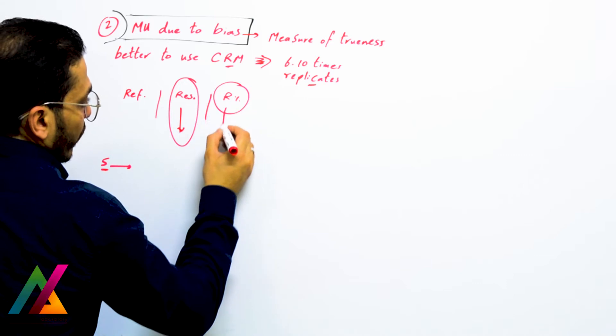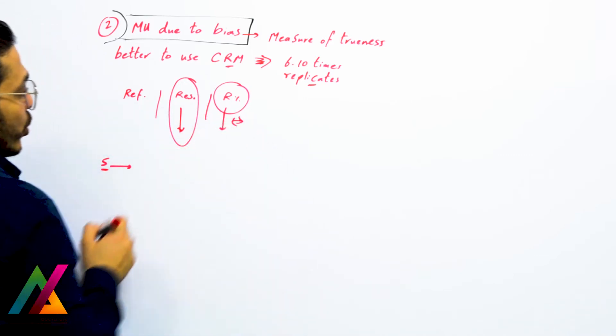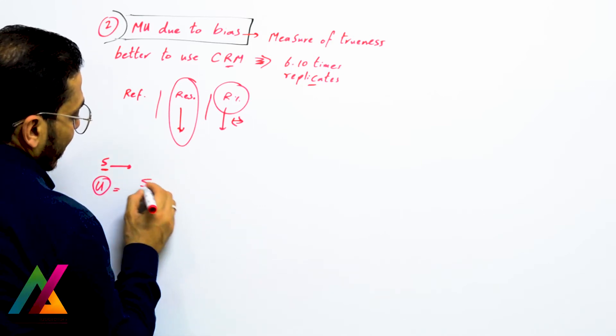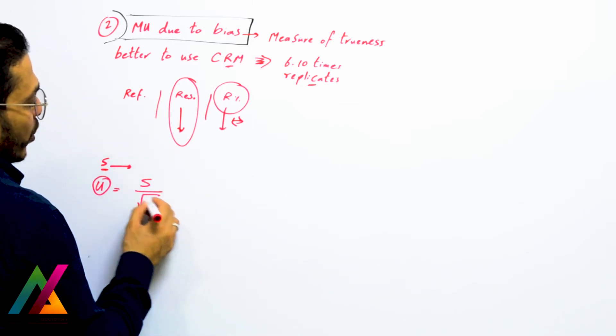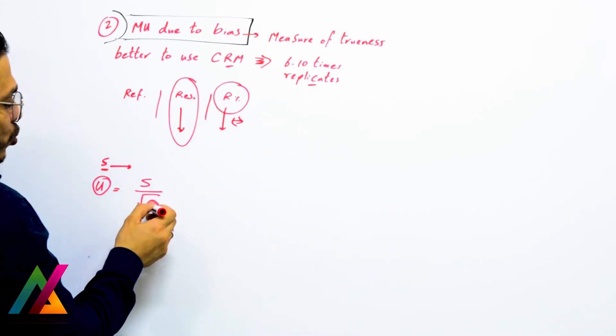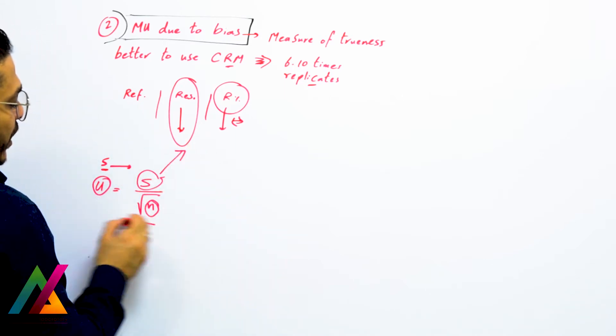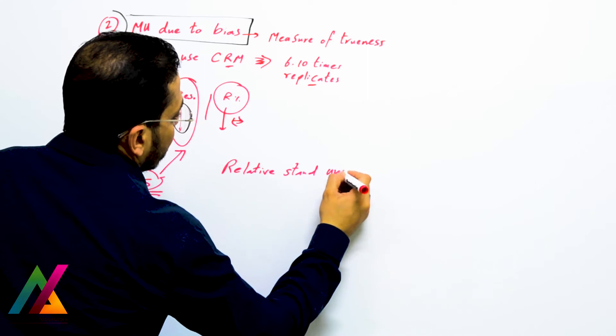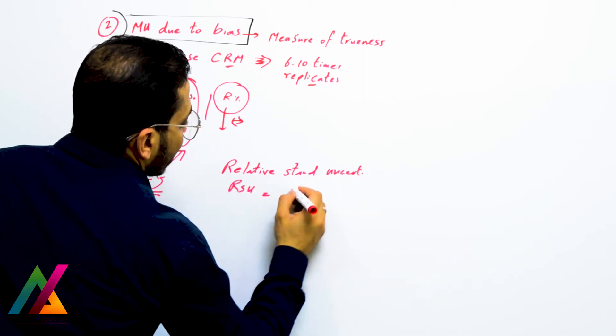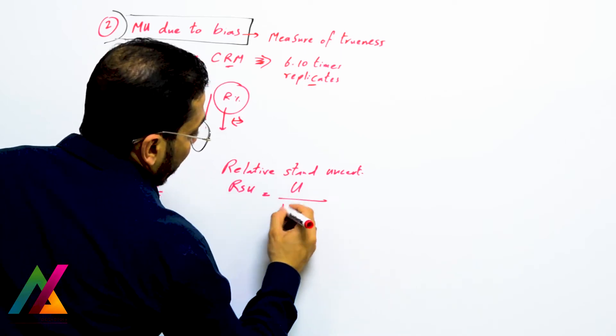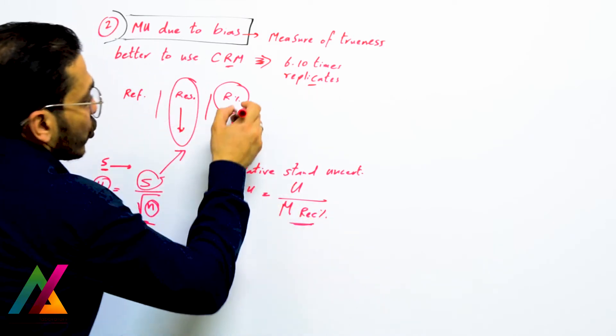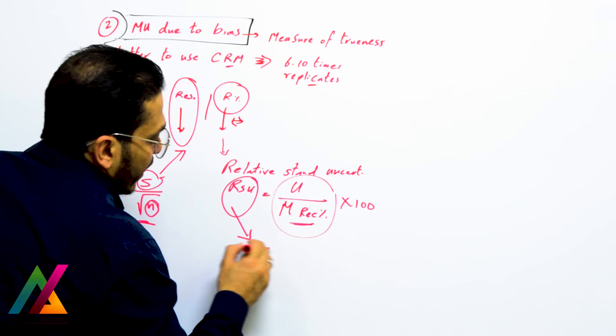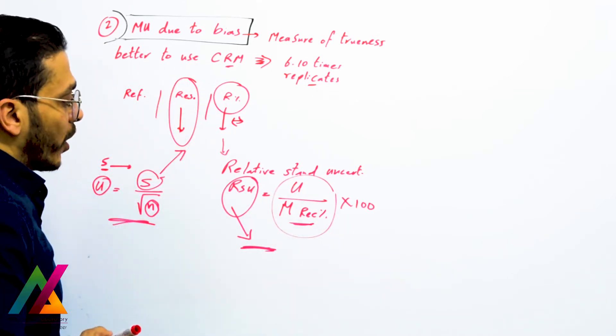From the results you calculate the standard deviation between all replicates. Recovery for each individual result should also be within the acceptable range. Then you calculate the standard uncertainty, which equals the standard deviation divided by the square root of n (the number of replicates). Then you calculate the relative standard uncertainty, which equals the standard uncertainty divided by the mean recovery, multiplied by 100. This relative standard uncertainty is your measurement uncertainty value due to bias.